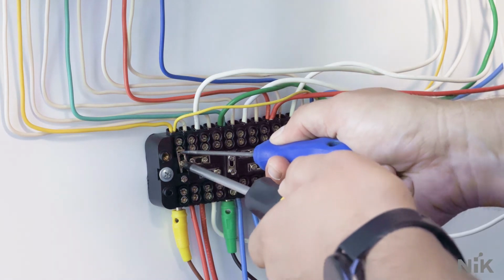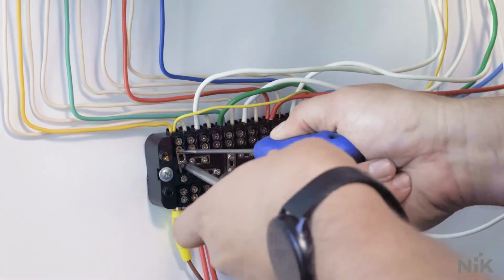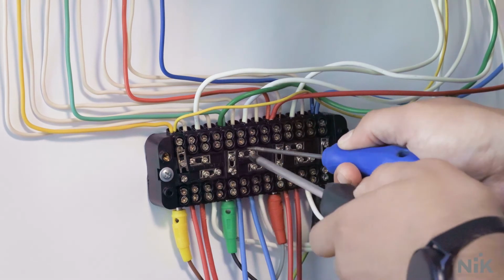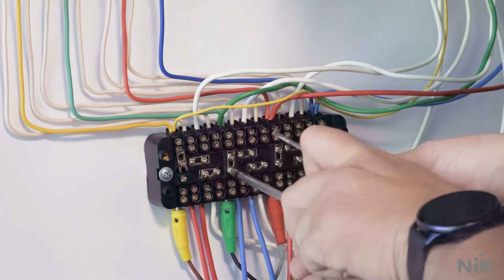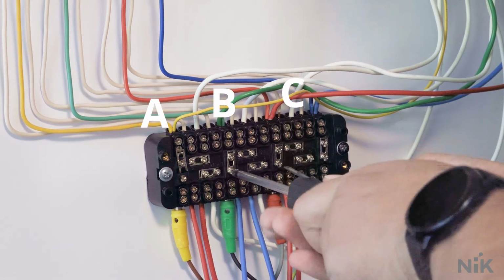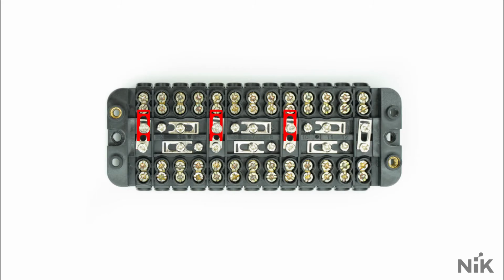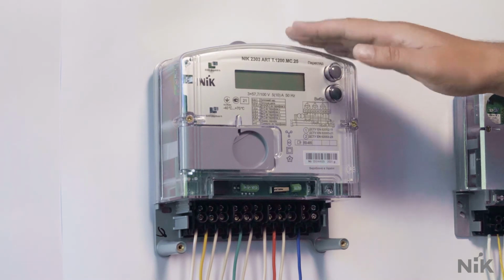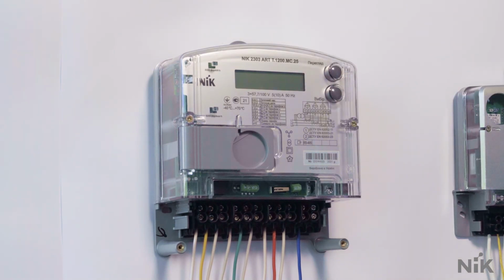We unscrew vertical jumpers and push them up. We can see the disconnected circuits on all 3 phases, A, B, and C. Neutral will remain untouched. The device is completely disconnected. After this, we can unscrew the wire and can dismantle the device from the metering point.